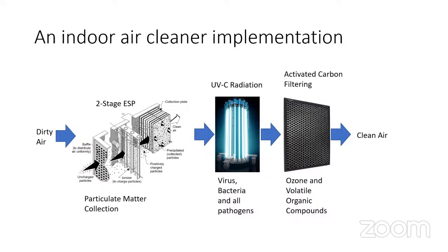Right now, sir, what they've done is, they went ahead, corporate R&D at Haridwar. They've installed one pollution control tower in the Noida campus. But it worked for only a few months. They had some problem of choking. Now they've stopped it. But they have not implemented two stages. Instead, they went for a fabric filter. They were getting a lot of choking issues, and again they are trying different options. But this can also be tried. They were actually coming back to us, but we said it has to be first tested in outdoor conditions. Then after that they didn't come.